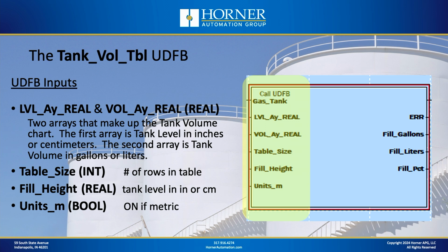All right, so fill height is another real value that correlates to the liquid in the tank in the same units that your table is expressed in. So if your table is in inches, your fill height would need to be in inches, for instance. And then there's one more input that is just a Boolean on or off, and if it's on, it means that your table is in metric units.